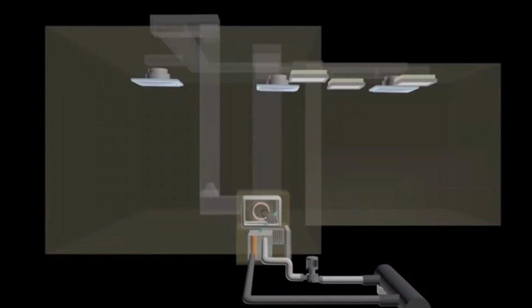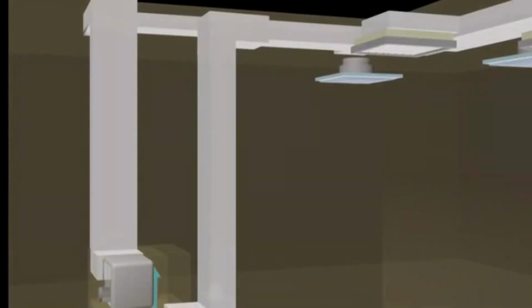The airflow system is operated using an auxiliary fan which creates the air cycle, taking air from the room and mixing it with fresh air from the outside into the air handling unit and returning it back to the room. The type of fan used is a centrifugal fan, powered by a motor and connected through a belting. The channel the air flows through is called ducting.